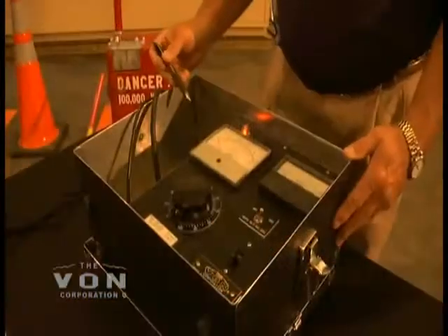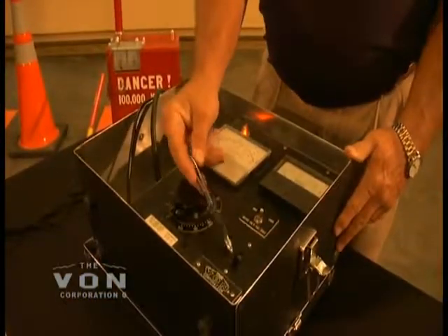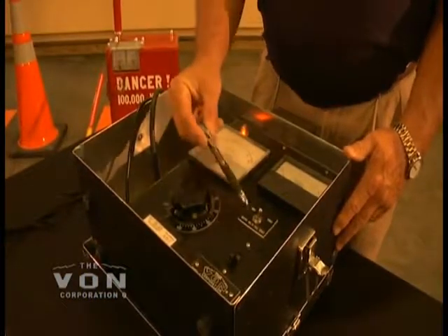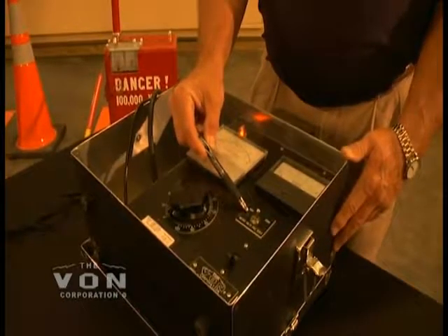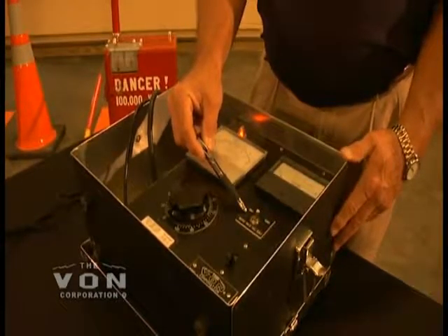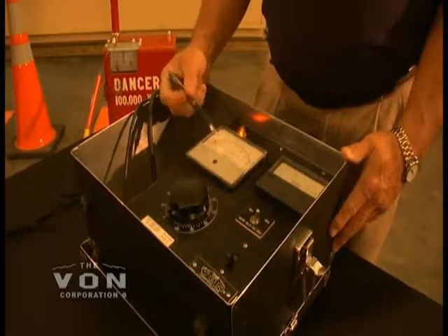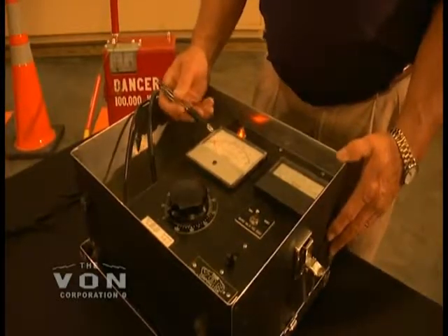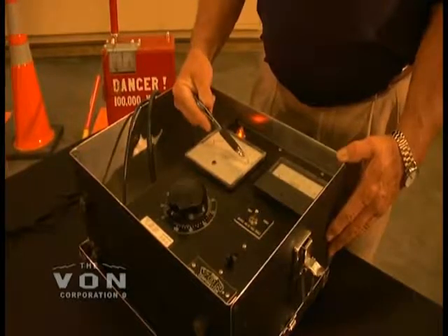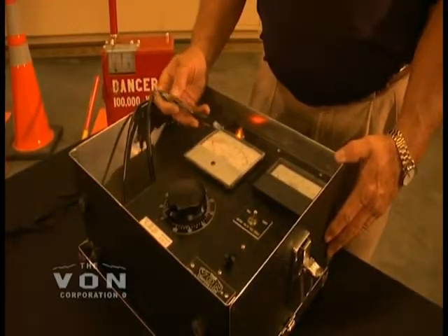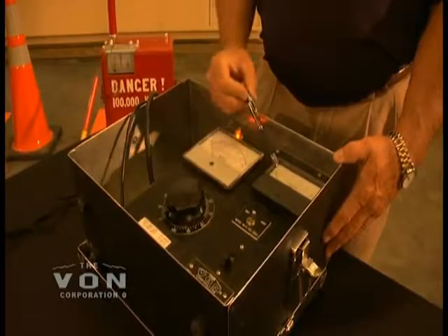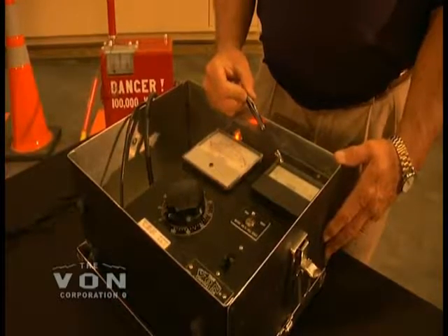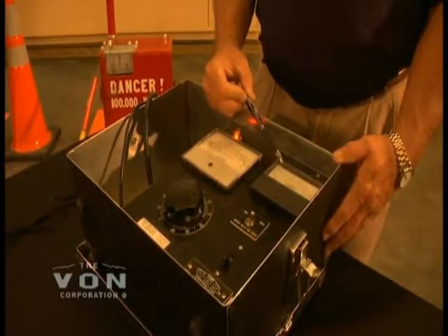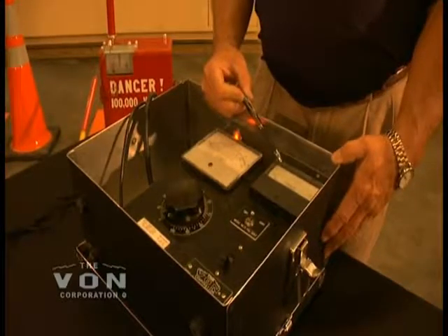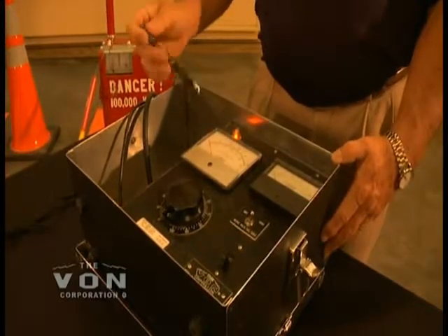This is the main control unit for the C1. It consists of your on-off switch, your voltage output switch of either 30,000 volts or 100,000 volts. That corresponds to your DC kilovolt meter. Your lower scale is 0 to 30,000. Your upper scale is 0 to 100,000. This is your AC amp meter, which allows you to make sure that the unit is connected properly and lets you know what amperage you're drawing. This is your dial to dial your voltage up.